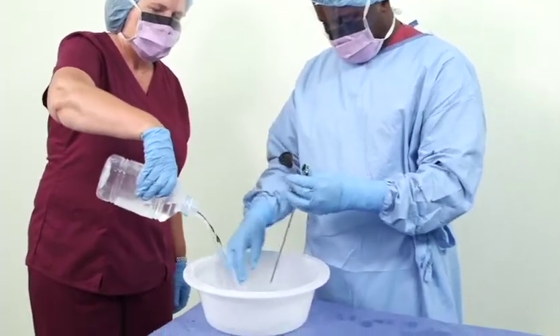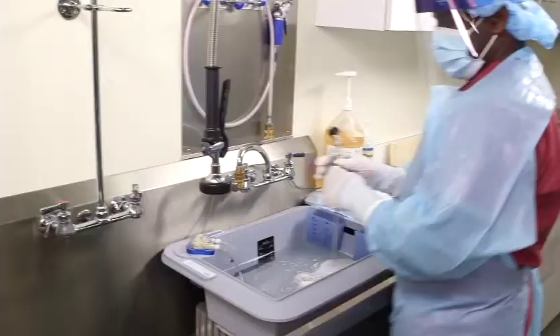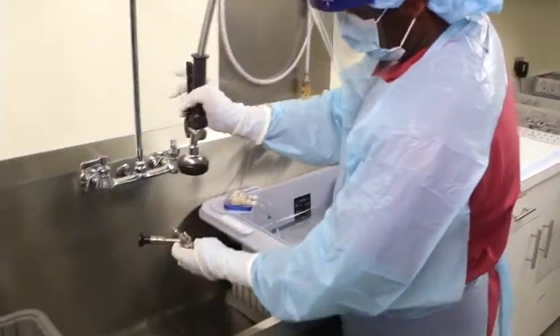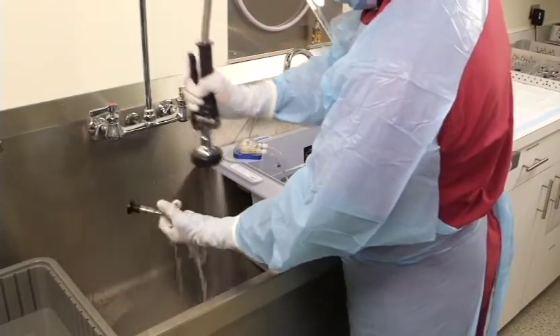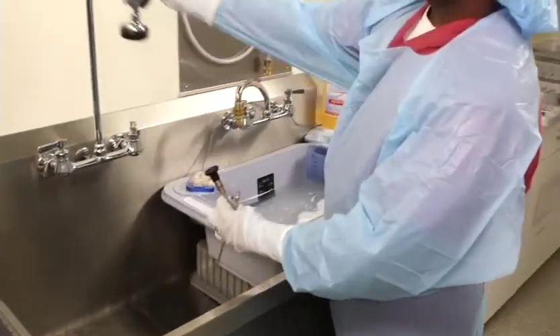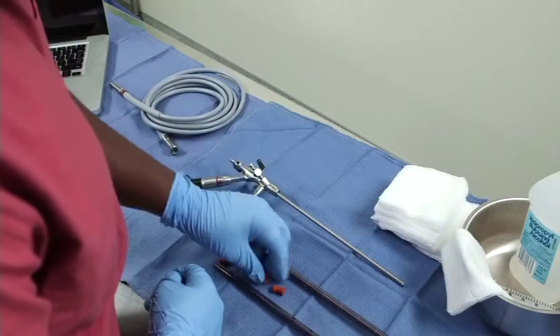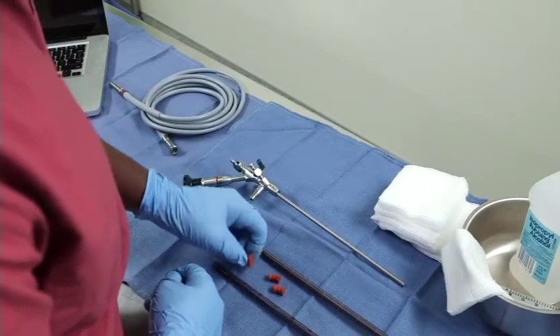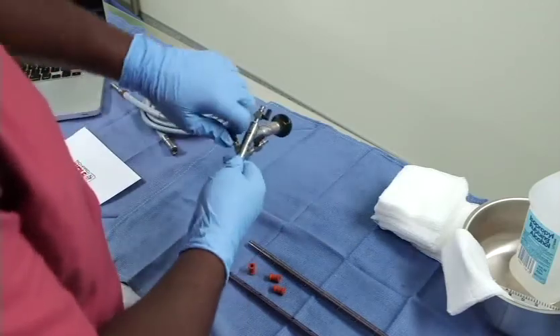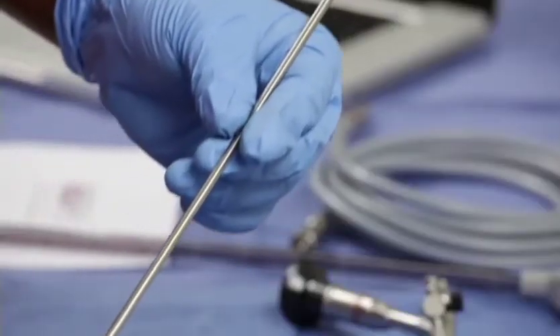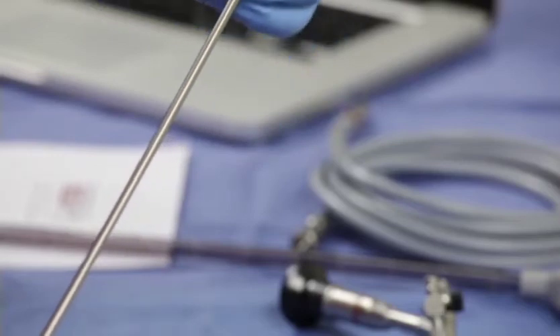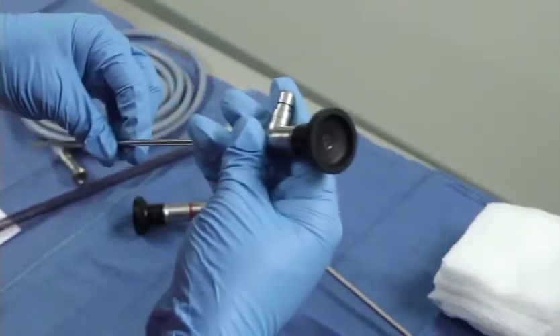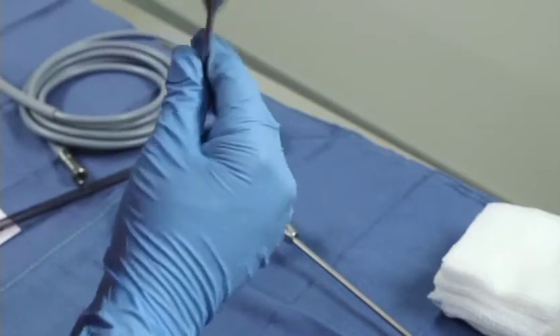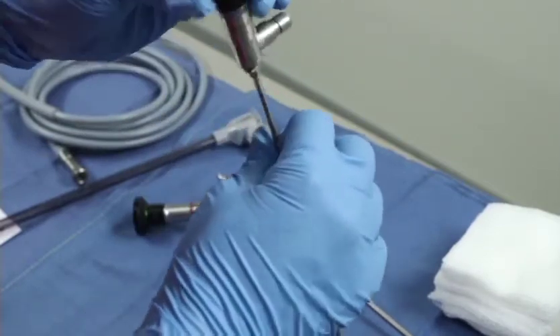If high-level disinfection is used in the decontamination process, rinse the endoscope with processed water as per the chemical manufacturer's instructions, thoroughly dry, and transport to the assembly area for inspection. The endoscope and parts are now ready for inspection in the assembly area. Inspect the endoscope adapters, stopcocks, caps, and any other parts that attach to the endoscope to ensure that they are in good working order. Check the rigid endoscope shaft for scratches, dents, or evidence of laser burns. Next, inspect the eyepiece lens and the optical lens for any cracks, scratches, and fogging or loose epoxy.